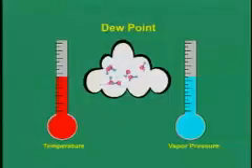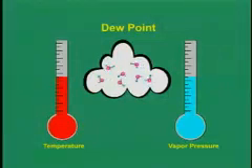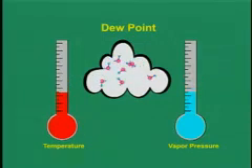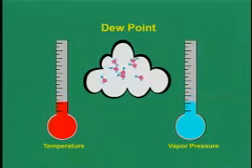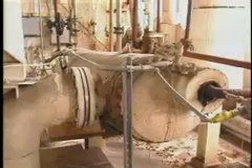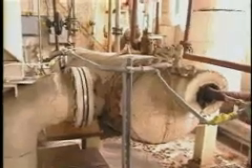The ultimate efficiency of a condenser depends on the operating temperature. As a vapor-laden gas stream is cooled, the molecules slow down and crowd together so closely that weak electrostatic forces between the molecules cause them to condense. The point at which this occurs is termed the dew point temperature. With further reduction in temperature, the vapor pressure of the condensing compound decreases. The lower the vapor pressure, the lower the concentration of the contaminant in the gas stream. Condensation systems generally operate at efficiencies greater than 90%.